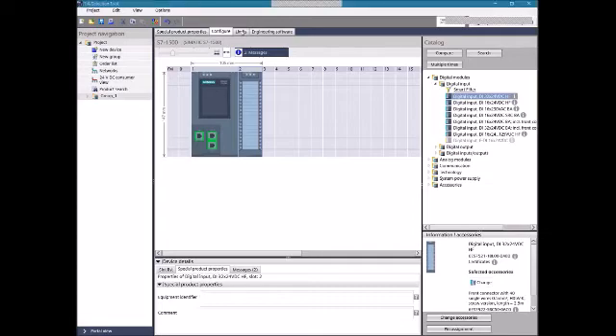Let's take a look at the other tabs up here. The Limits tab is a neat one. You can see we've got 105 millimeters of width for our modules. The Limits tab gives us a bunch of information: the height, width, depth, and which DIN rail was selected. There are also IO counts, and the power usage plus total peak current value — which is helpful when selecting a power supply for our CPU.